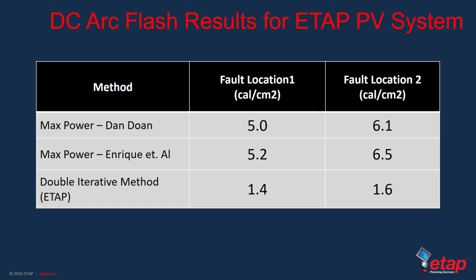The conclusion is that, at the time, the incident energy is over-predicted by a factor of at least 6 times. The over-prediction is expected to get worse as the size of the photovoltaic collector system increases. For a 1 megawatt or higher collector system, the prediction using the max power method, as explained by these two methods in row 1 and row 2, can easily exceed the 40 calories per centimeter squared range. But in fact, for those systems, the actual result is more likely to be in the 5 to 8 calorie range. Bottom line, for our 400 kilowatt photovoltaic system, our method predicted about 1.4 to 1.6 calories per centimeter squared, which is about 6 times less than what is predicted with these other methods.